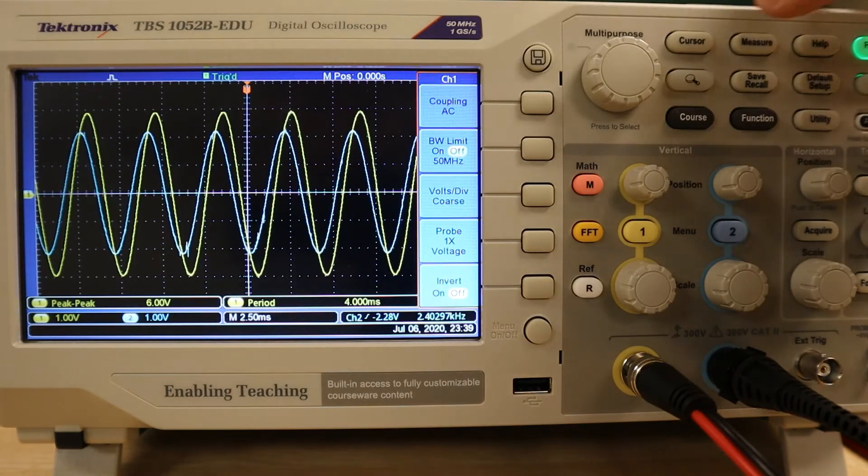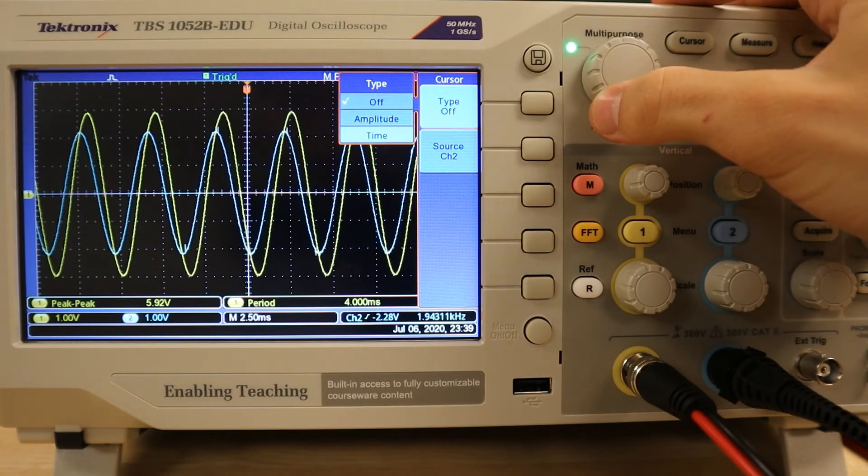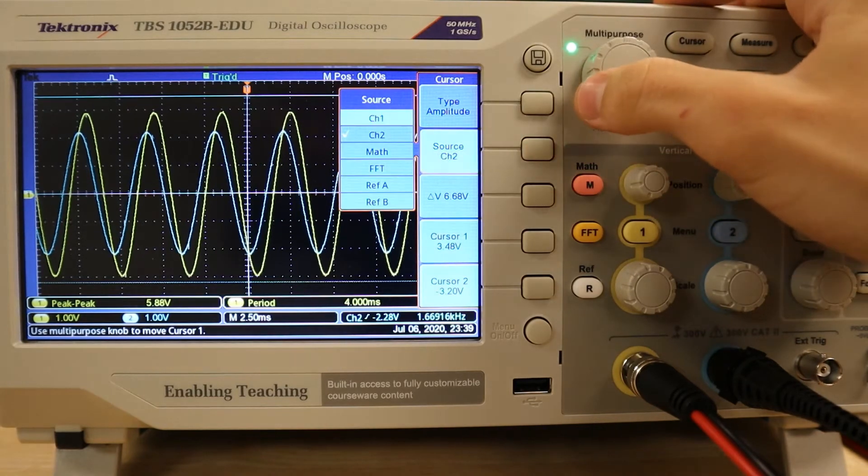To use the cursor, we'll select the proper button, which will allow us to change the cursor between measuring voltage or time. We also have a choice between measuring along the plot of channel 1 or 2.